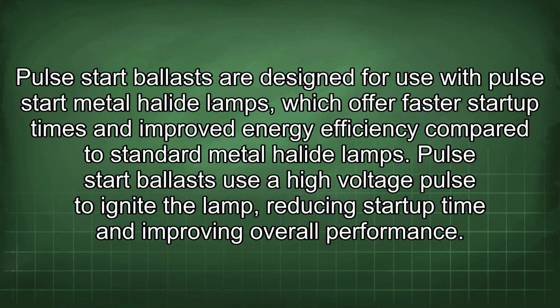Pulse start ballasts are designed for use with pulse start metal halide lamps, which offer faster startup times and improved energy efficiency compared to standard metal halide lamps. Pulse start ballasts use a high voltage pulse to ignite the lamp, reducing startup time and improving overall performance.